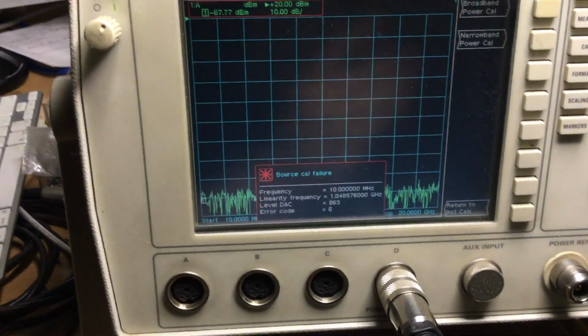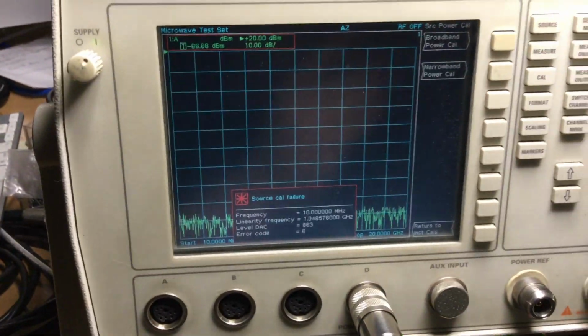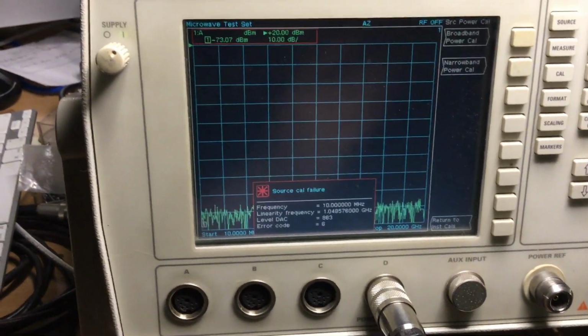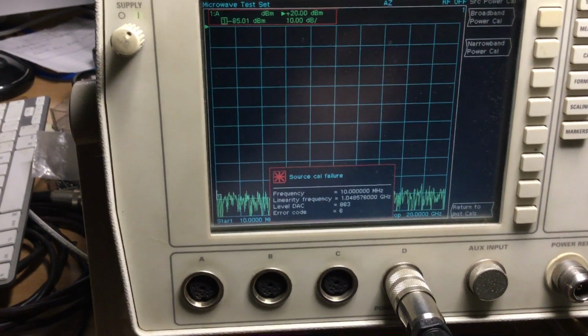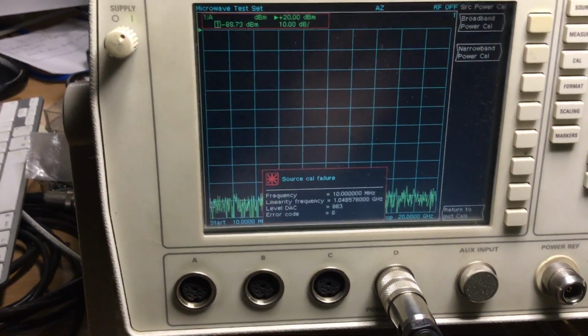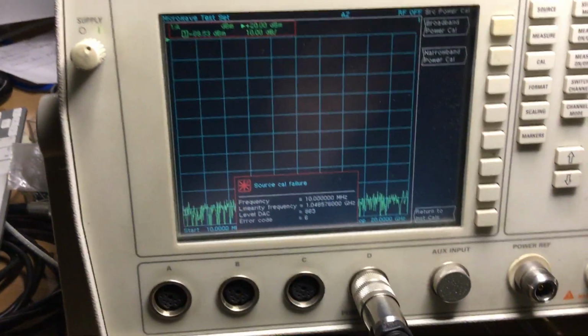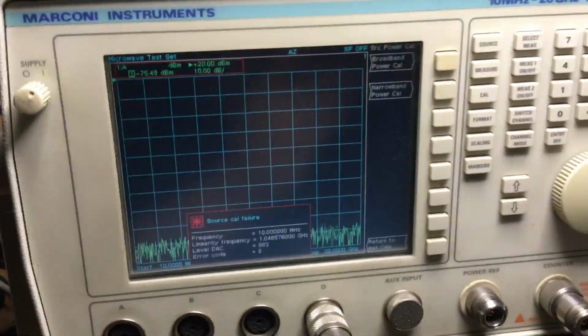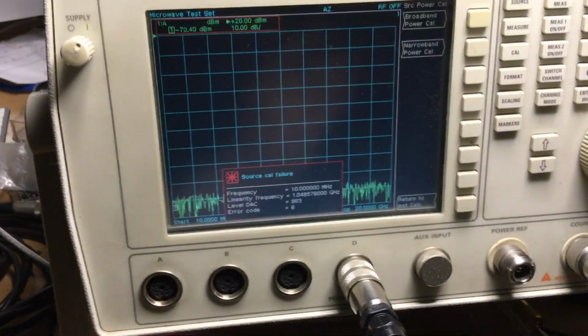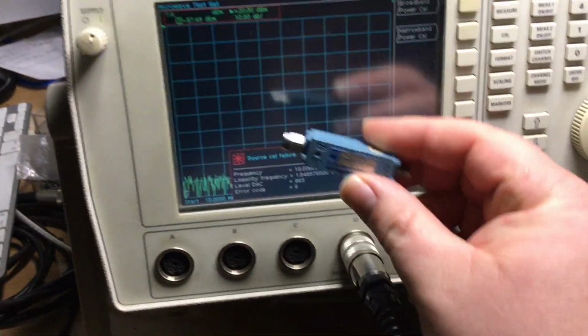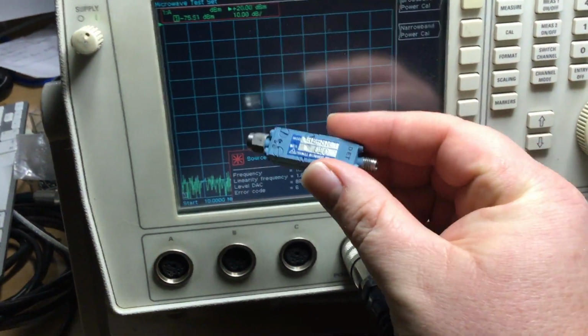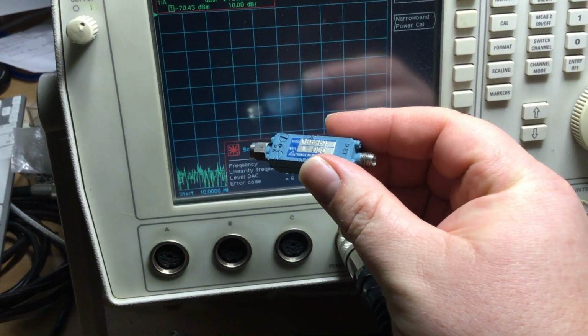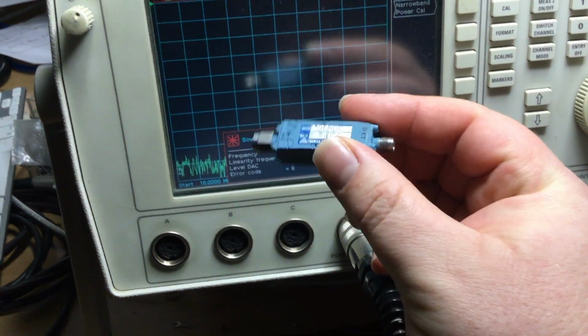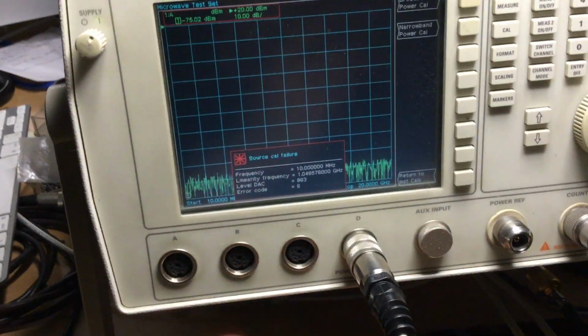As I said, it's got to be able to resolve 0.5 to 1 dB steps across the entire level range, across the entire frequency range. If you can't accomplish that, then I'm afraid it won't calibrate. That's why it's important to either get the right parts for the test set or something equivalent. So I think we're going to try this next, and if that works, then I'll come back to you and I'll show you the calibration again, and we'll install this. So all is not lost.